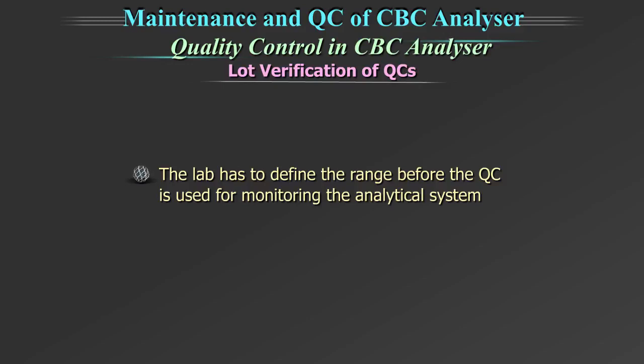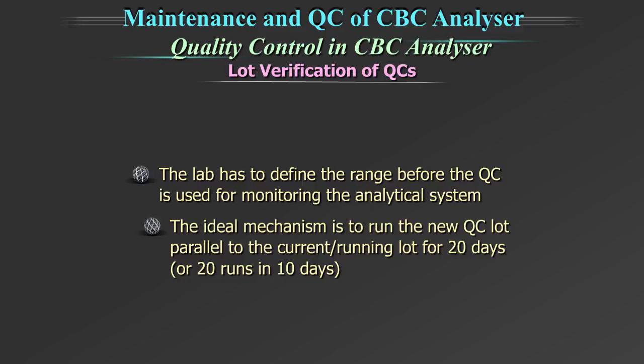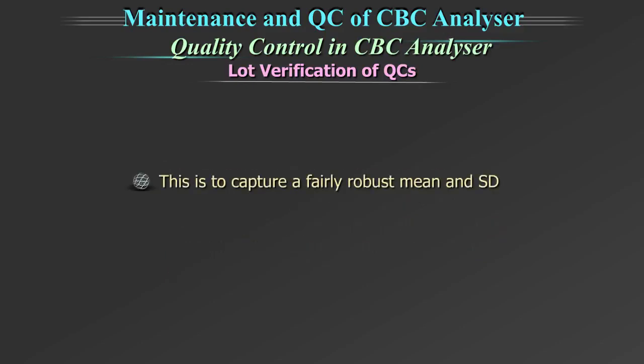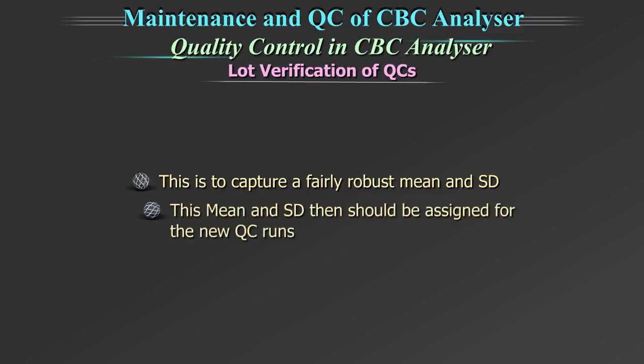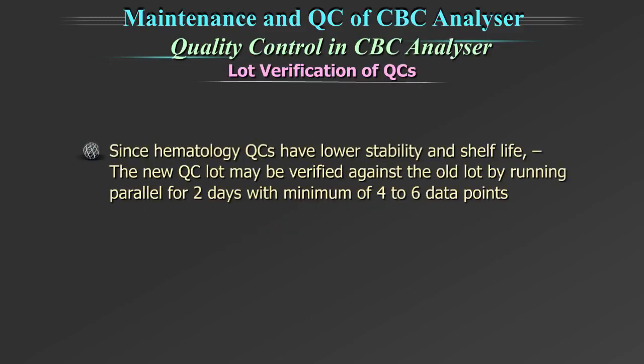analytical system. The ideal mechanism is to run the new quality control lot parallel to the current or the running lot for 20 days or for 20 runs in 10 days. This is to capture a fairly robust mean and standard deviation. This mean and standard deviation then is assigned for the new quality control runs. However, hematology quality controls have lower stability and shelf life.